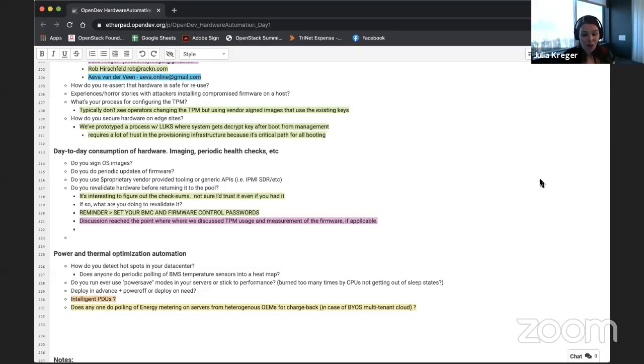So you'd have to go all the way from the entrance, transfer switch, UPSs if you're there, transformers, and then there has to be enough correlating information to make it all the way down to the PDUs to be able to balance that load out. And then you have to be able to graph it and correlate that and display it and allow logic and humans to make decisions from there.